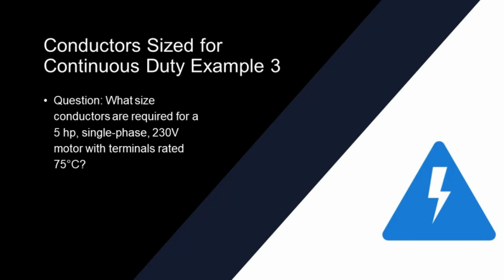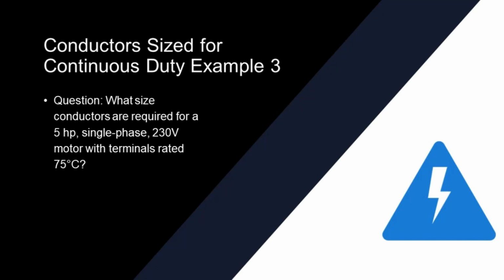All right. Conductor size for continuous duty example number 3. What size conductors are required for a 5 horsepower single phase 230 volt motor with terminals rated at 75 degrees? So I will go to 430.248 for a single phase motor. I roll down to 5 horsepower. I look under the 230 volt category and I see 28, right? So I'm at 28.